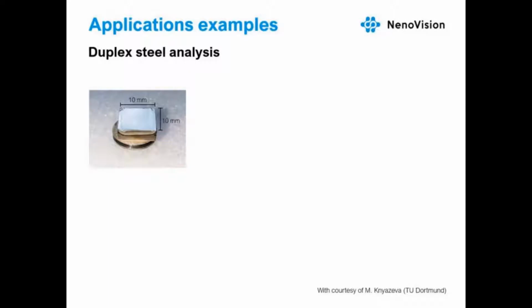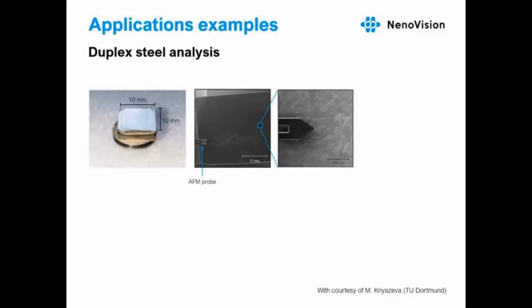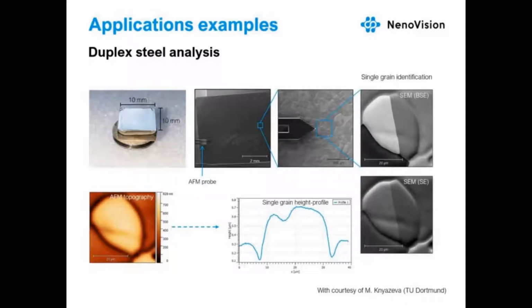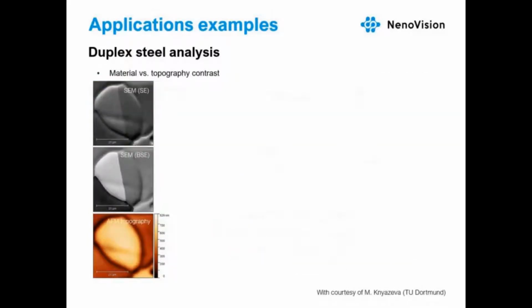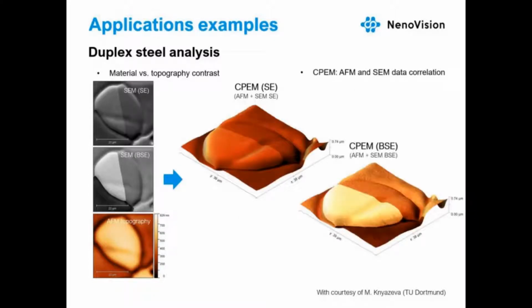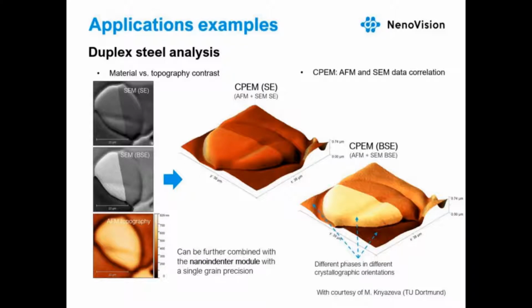So one of the nice examples of the AFM-in-SEM combination benefits is the analysis of Duplex steel, where you can identify individual steel grains, precisely measure their topography, and nicely distinguish between 2 different steel phases. And the result is a fantastic correlation of topography with SE and BSE signals from SEM showing strong contrast of individual metal phases. So correlative CPEM imaging provides ideal tool for multiple data analysis. And also this application is an ideal candidate for the nano-indenter module, which enables nano-indentation with a single grain precision.